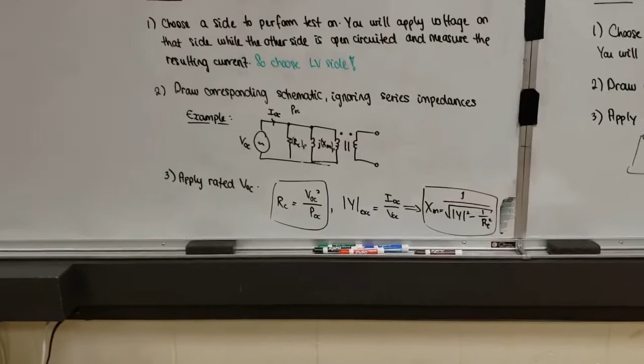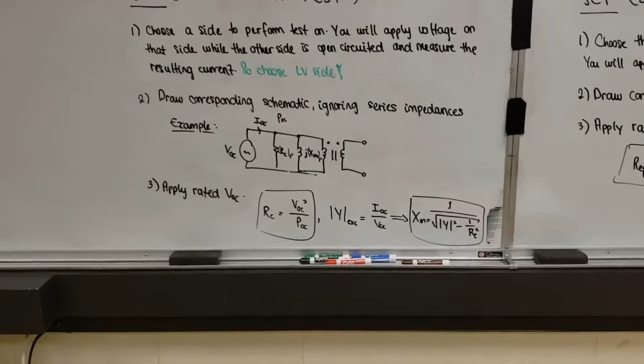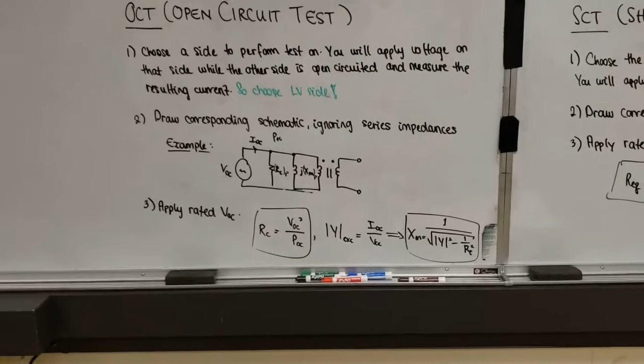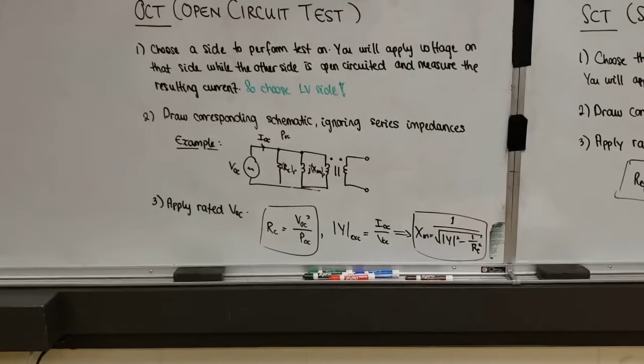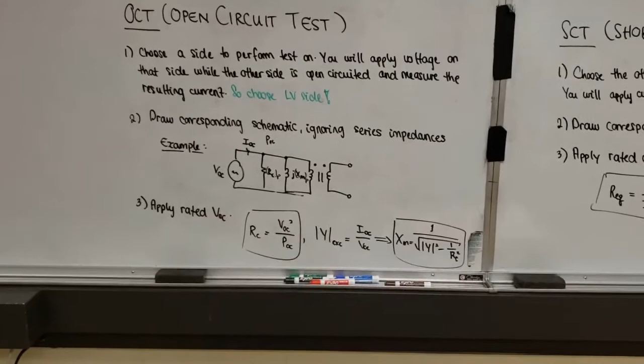We have two tests: the open circuit test and the short circuit test. I'll note, and this is something I observed experimentally last semester when I made this lab manual, that the open circuit test has important limitations, which I'll mention, but the short circuit test not so much. The open circuit test allows you to gain those parallel branch, shunt parameters, and the short circuit test gives you those series parameters.